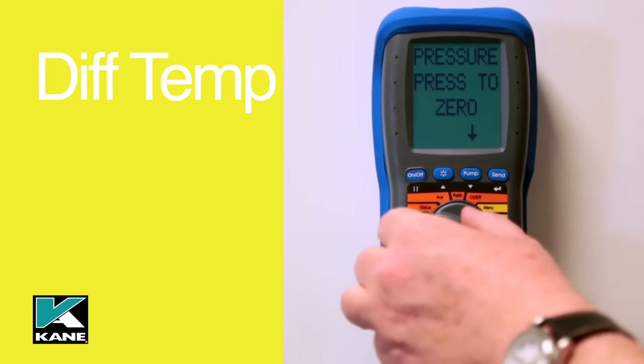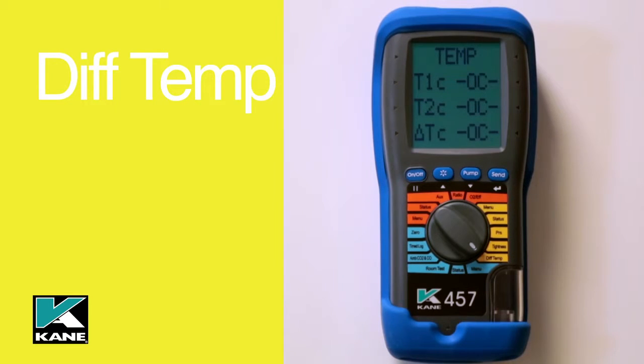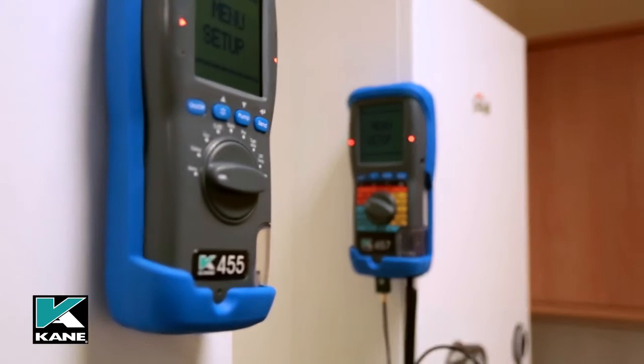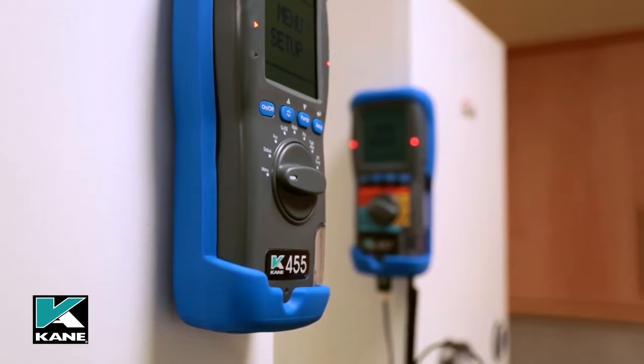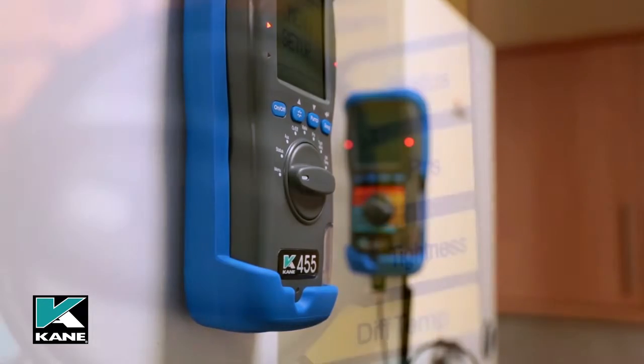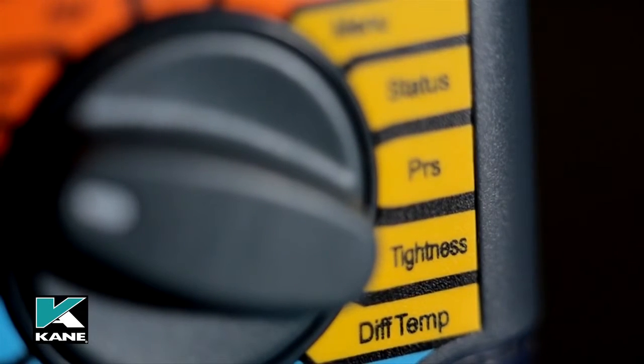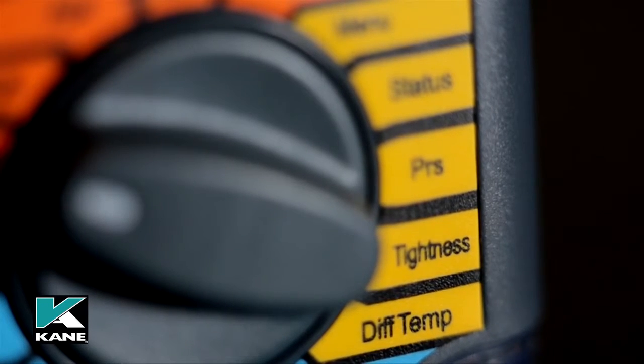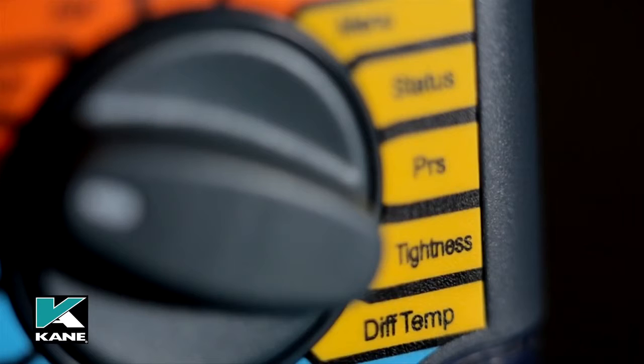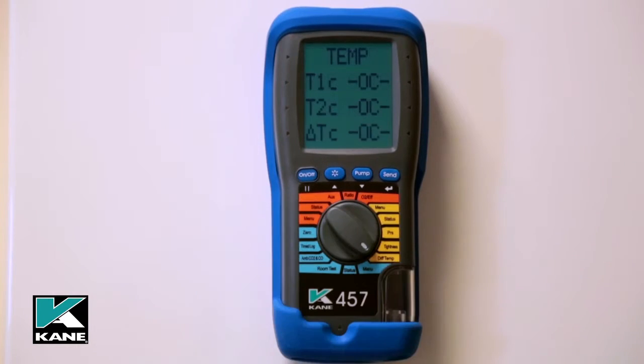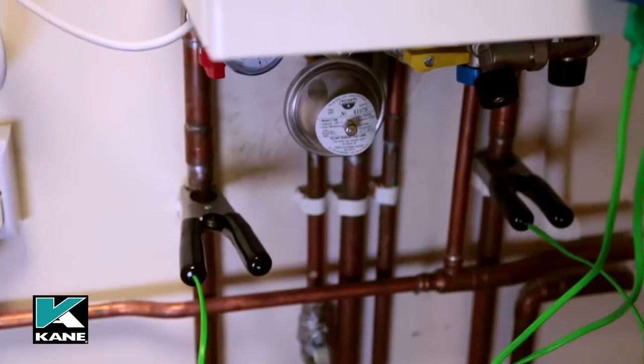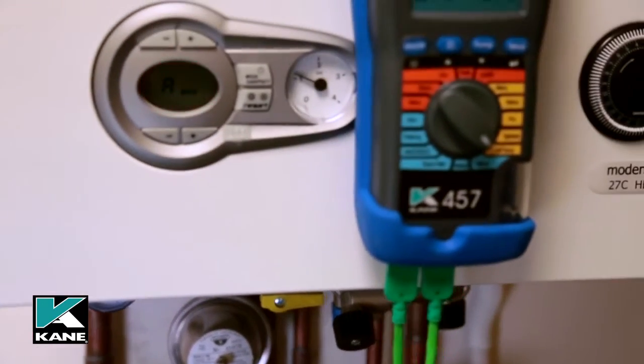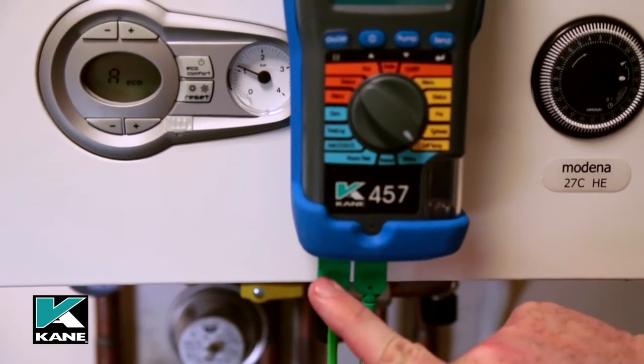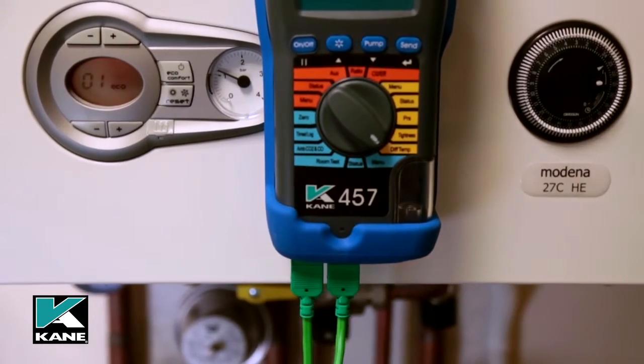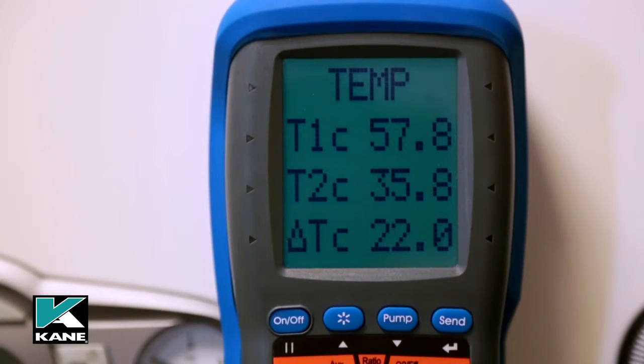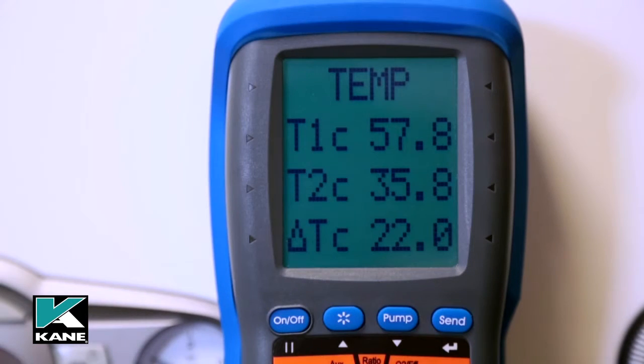The final option in the yellow section is differential temperature. This function also operates in exactly the same way as the KANE455. Using the KANE457 to measure the flow and return temperature of a boiler, select Diff Temp to measure single and differential temperatures. The pump automatically switches off when the dial is moved to Diff Temp. Connect the pipe clamp probe to T1 and T2 of the analyzer and then to the appropriate pipe work. The display will now show T1, the temperature of the flow, T2 the return, and the differential temperature.